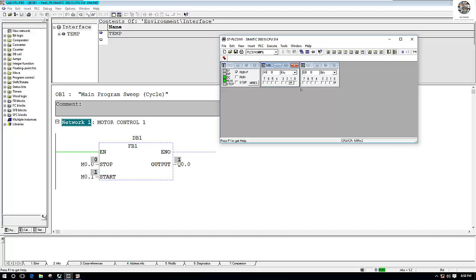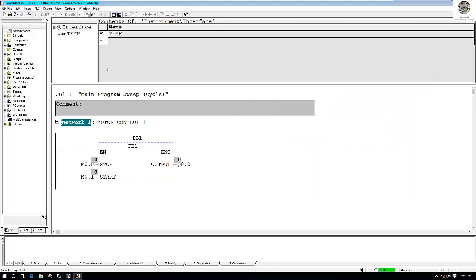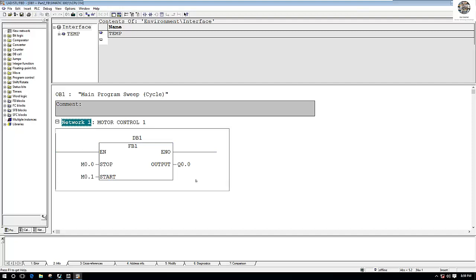Q0.0 is ON when M0.1 is ON. If I want to stop, I just turn ON M0.0 — and it stops. So it is the same as the ladder logic, but if we create a function block, you can apply it to more blocks without creating the same logic again each time.